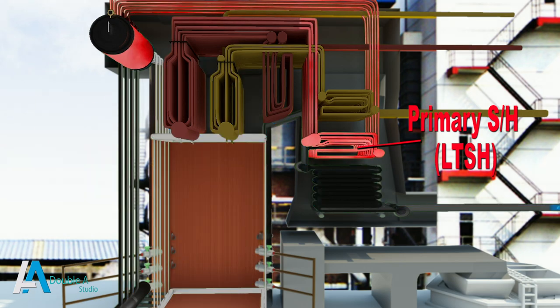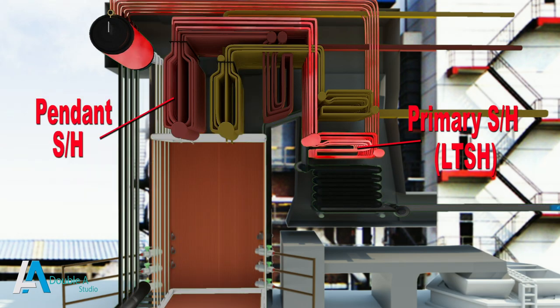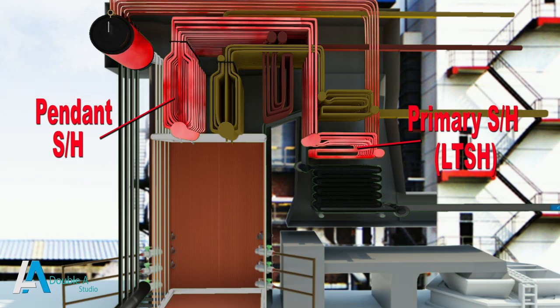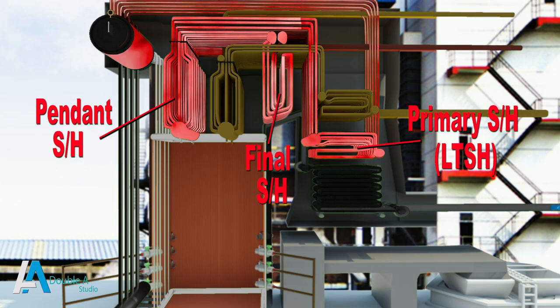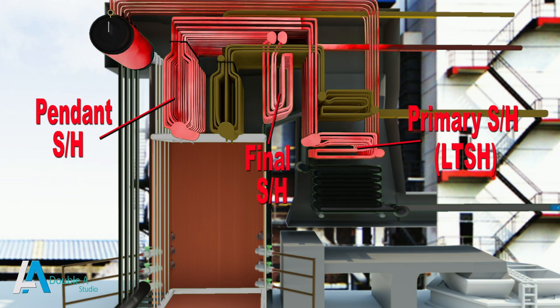After exiting the primary superheater, steam goes to the pendant type superheater, which is located in the roof section of the boiler. Here steam is further heated up and then goes to the final superheater, which is a radiation type superheater. After these stages of heating, saturated steam gets converted into superheated steam. In the final superheater, the rise in temperature of steam is much more as compared to the heat transfer that takes place in the primary superheater.